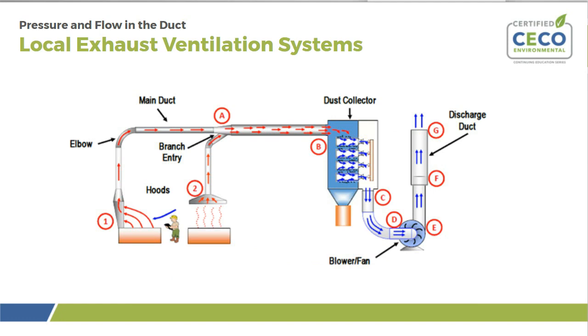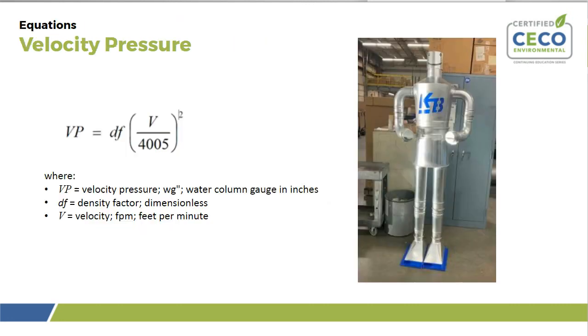Pressure and flow in the duct. Now let's use velocity pressure and static pressure to further define the flow of air in a duct. Our first important equation is the velocity pressure. Velocity pressure is Vp, and then we also have our density factor, df. V equals the velocity, which is always feet per minute. If we know the velocity pressure, the velocity of air flowing in the duct can be determined. This is the first equation allowing us to determine the air flow based on velocity pressure.